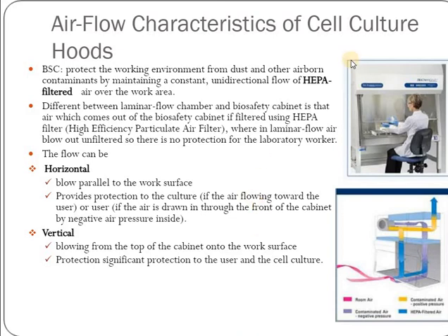The airflow characteristics of cell culture hoods are: they protect the working environment from dust and other airborne contaminants by maintaining a constant unidirectional flow of HEPA filtered air over the work area. The difference between a laminar airflow chamber and a biosafety cabinet is that air which comes out of the biosafety cabinet is filtered using a HEPA filter, that is high efficiency particulate air filter, whereas laminar airflow blows out unfiltered, so there is no protection for the laboratory workers. The flow can be horizontal, that is parallel to the work surface.